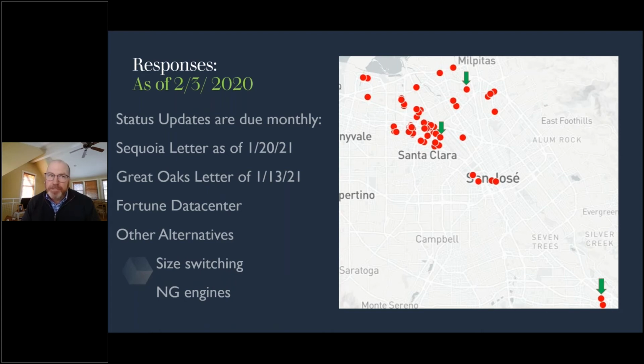Some other folks are looking at other ways for compliance - size switching. What do I mean by that? Again, this rule affects engines over 1,000 horsepower. If you were going to put in a 1,200 kW unit, you can split that into two smaller engines. If you wanted to do two 600 kW units, you could net out of this rule. And then some folks are considering switching to natural gas.